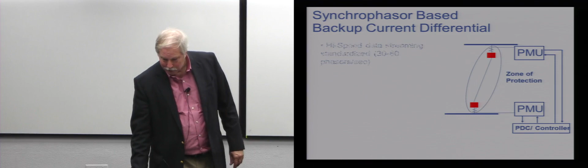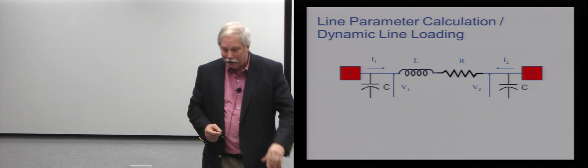Synchrophasors can be used for dynamic line impedance calculations. By measuring synchrophasors at both ends of the line, I can do a very simple Kirchhoff's voltage rule: sum of the voltages equals zero. So V1 plus the voltage across the line plus V2 equals zero. By taking synchrophasor measurements at the two ends of the line, I can compute the voltage equation and literally compute the dynamic line impedance.